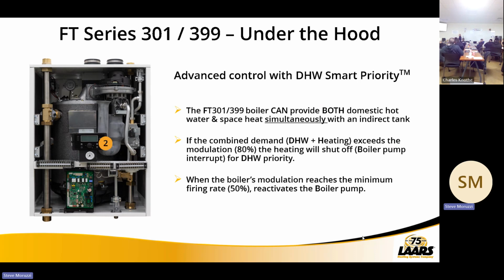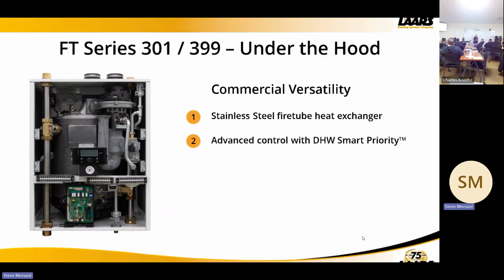We can provide both heat and hot water, so the indirect tank, heat to the zones and heat out to the indirect tank. And if we hit 80% of modulation, we want to control that boiler and system pump, and we're going to shut off that pump. I'm providing all the heat to the indirect tank. When we start to catch up and it modulates back down to 50%, we will re-energize that pump.